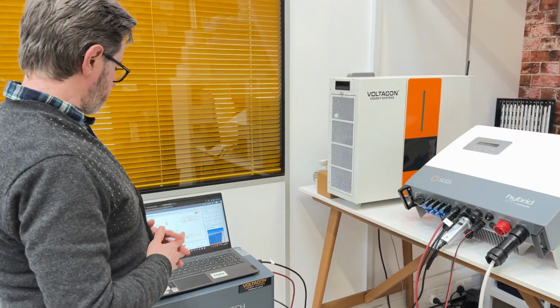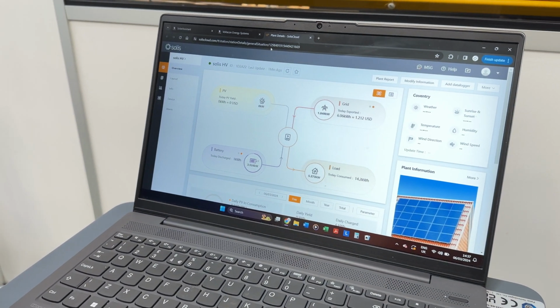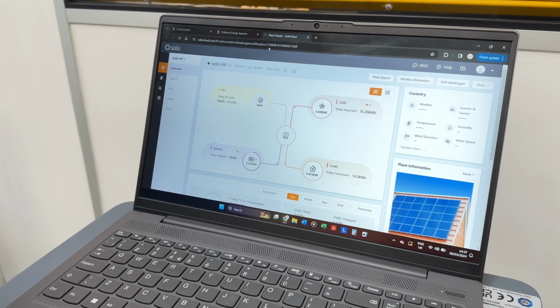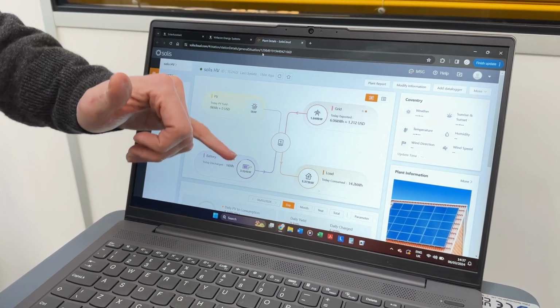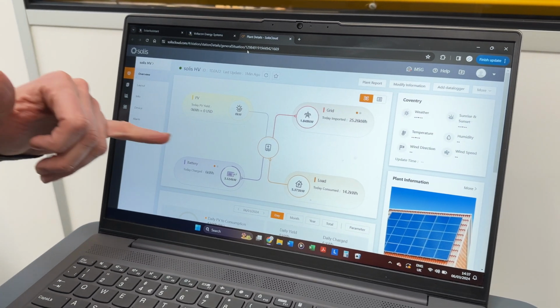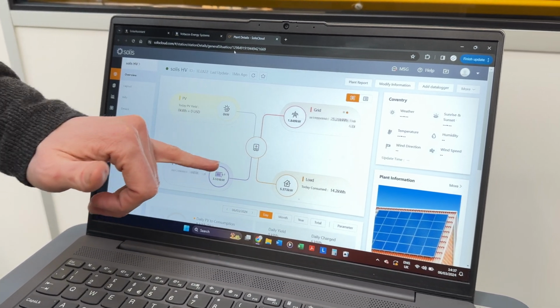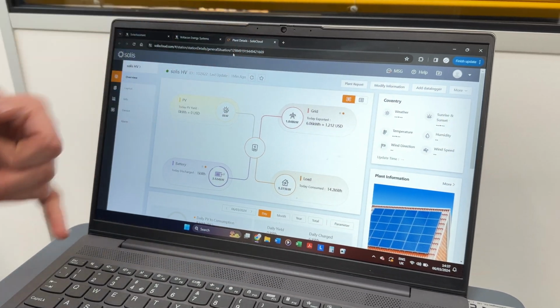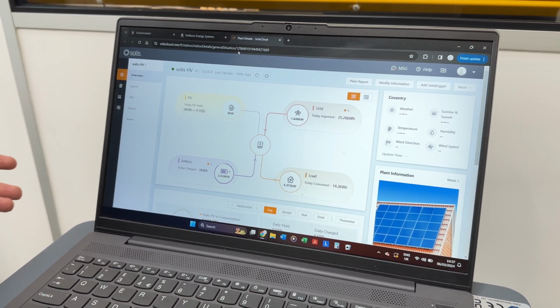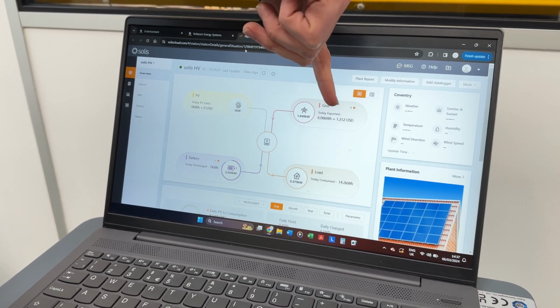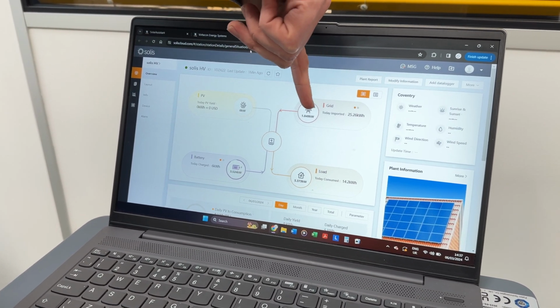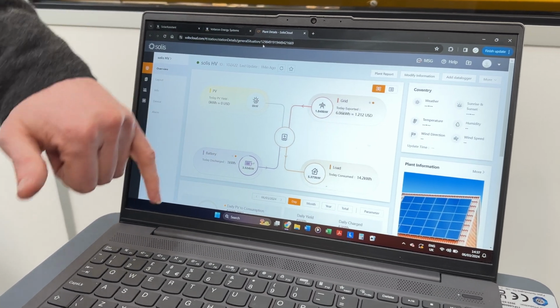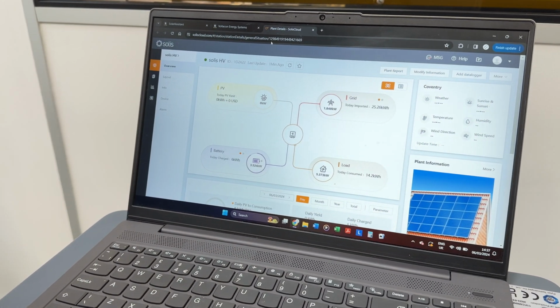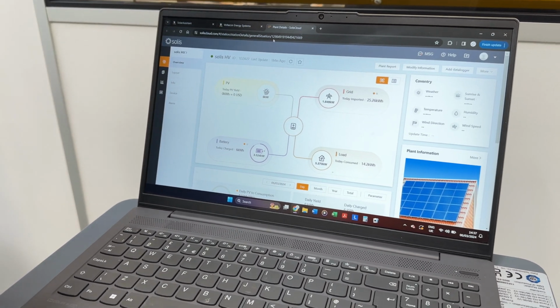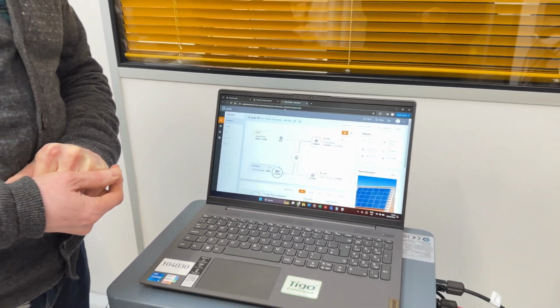Now, let's look at our Solis Cloud. As I said, this is a self-consumption facility. We generate electricity, we store it into the battery, and when we start the discharge, we feed the energy from the battery to the load. In this case, because our battery bank is very small, it's only 7.5 kilowatt hours, we need to take a little bit of energy from the grid. So if you add up 1.8 kilowatts and 3.5 kilowatts, you get approximately 5.3 kilowatts, and this is exactly how much our warehouse is consuming right now.